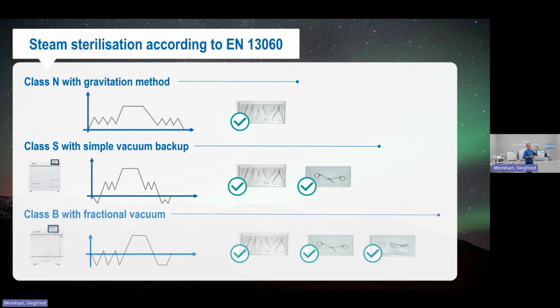You've then got, right at the other end of the spectrum, that full B-class, which the units you see here, these are all B-class units. So they're what we call full vacuum units, and loading is in exactly the same way. You're still loading the tray, instruments side by side. We're not multi-stacking instruments or anything like that, because that just inhibits where the steam gets to. They can accommodate everything that S can accommodate, but with the exception that they can also accommodate wrapped hollow hand pieces, wrapped hollow instruments. So that's the important thing.